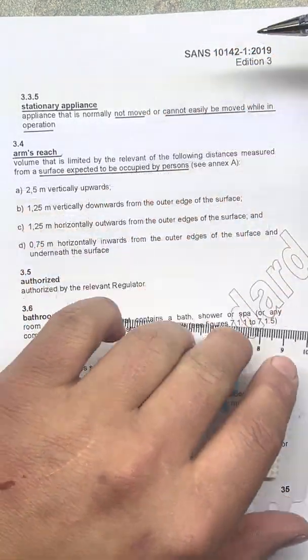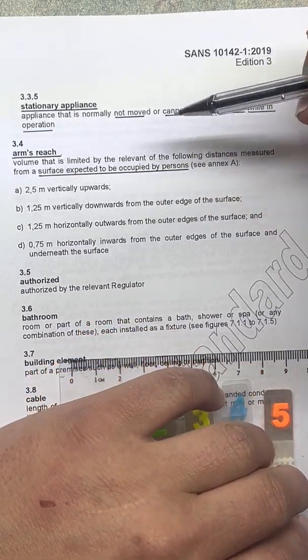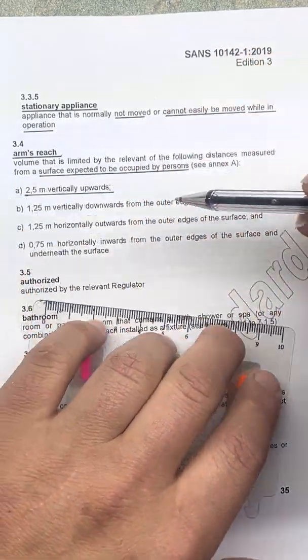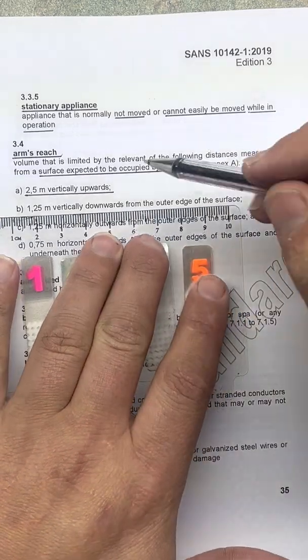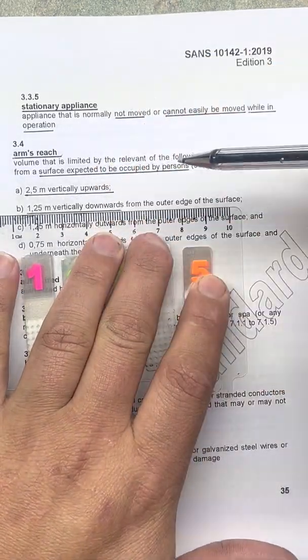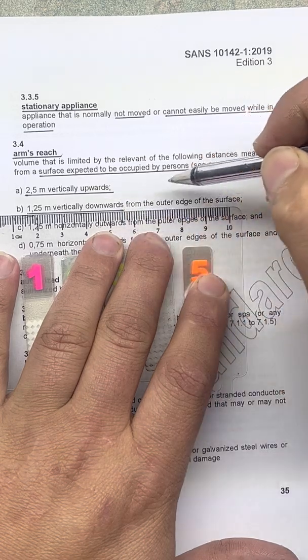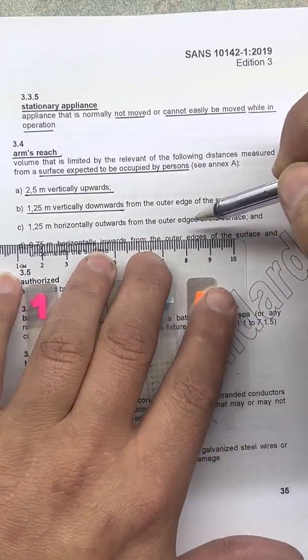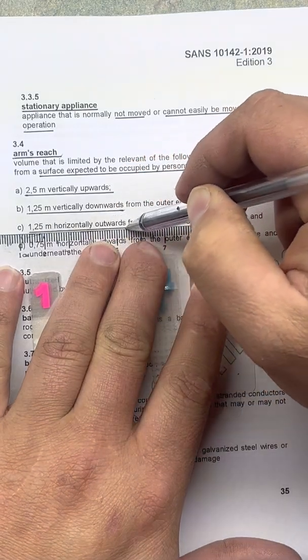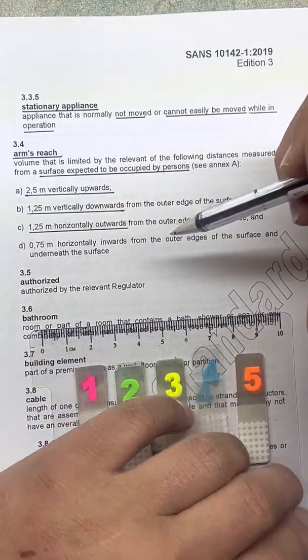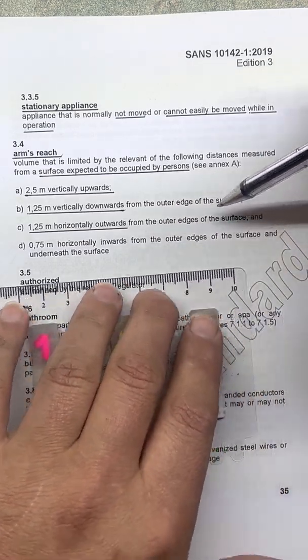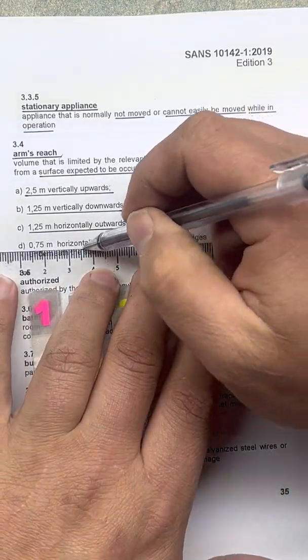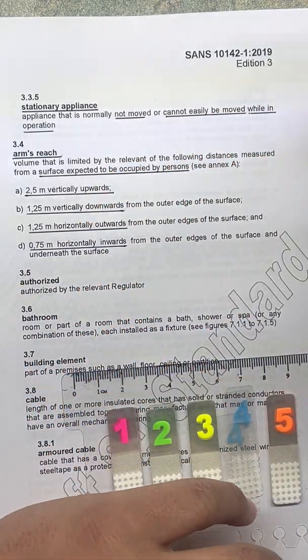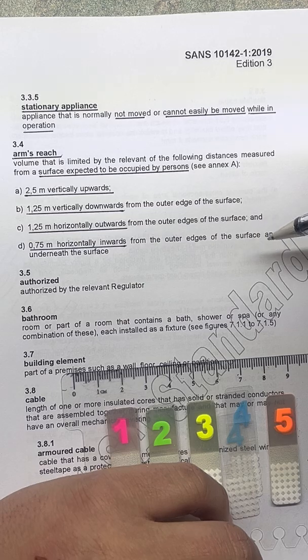So arm's reach is the surface expected to be occupied by a person: 2.5 meters vertically up, 1.25 meters vertically downwards from the outer edge of the surface, 1.25 meters horizontally outwards from the outer edges of the surface, 0.75 meters horizontally inwards from the outer edges.